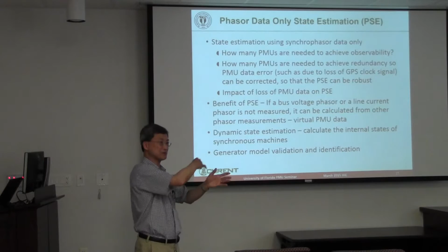In particular, we'd like to know the output of generators. But in New York, the generating substations' connection to the grid is normally owned by the generator owners, and they're not obligated to put PMUs on it. So what you have to do is use the neighboring bus, which has current phasors looking at it, so you can calculate it.